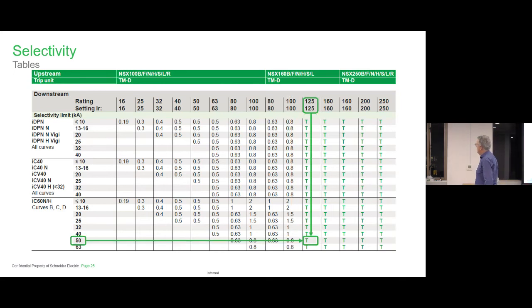So how do we overcome that? Well, just go up one size straight away. We can adjust this down a bit because it's a thermomagnetic, but with a thermomagnetic you've only got 0.7. So 0.7 times 125, we might get there, or we might not. So then we get into changing these to electronic trip units and so on. So you have options, you have a way through the design somehow.